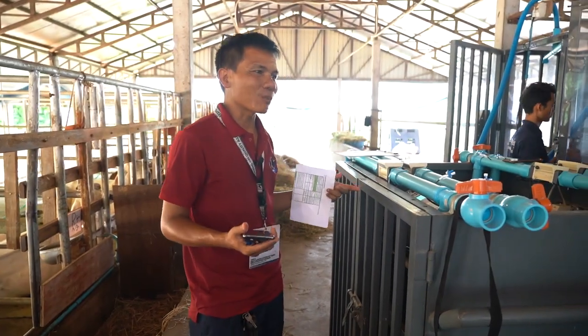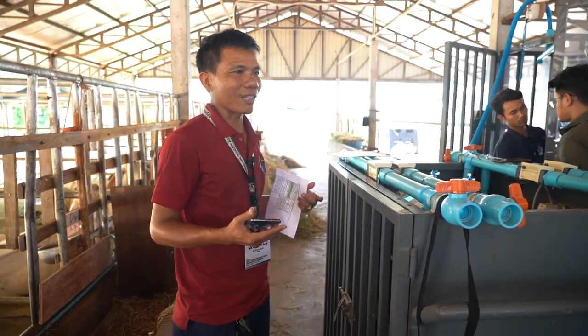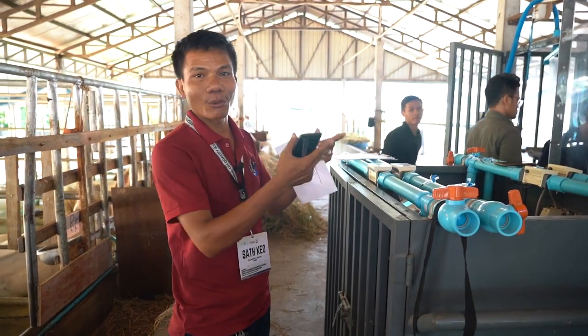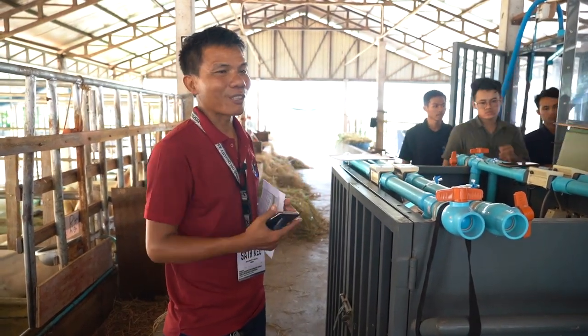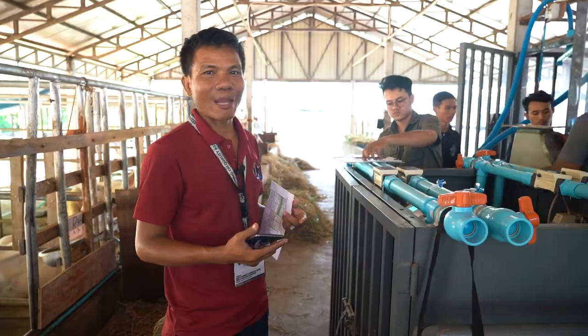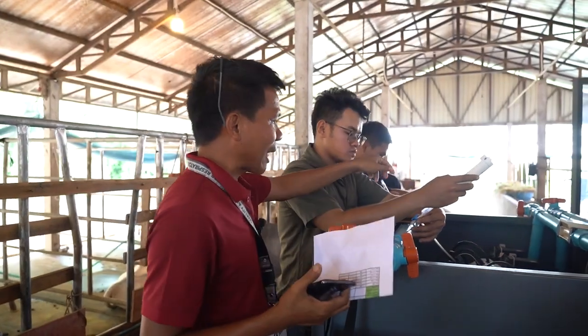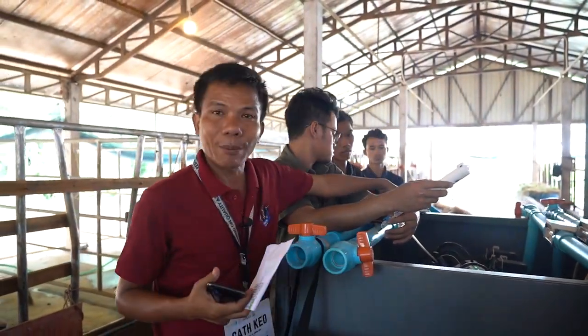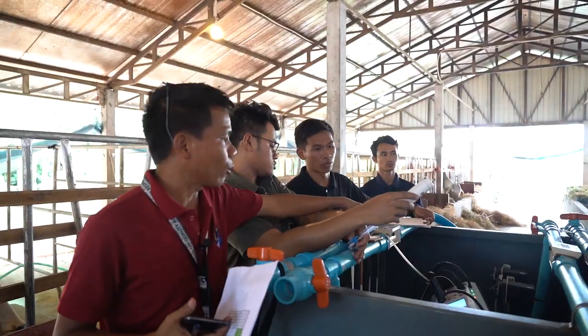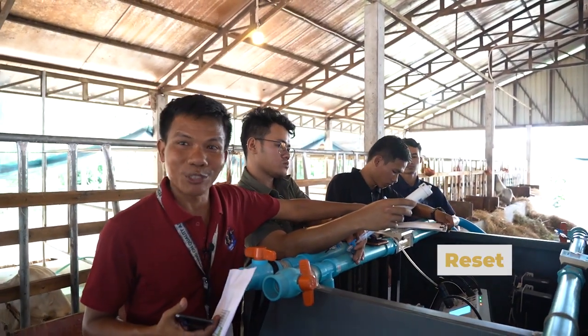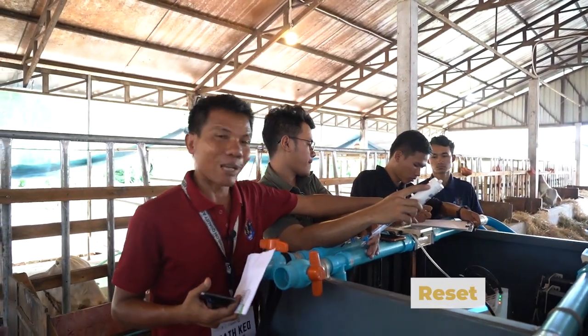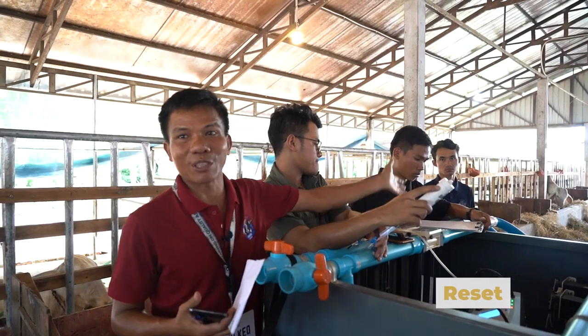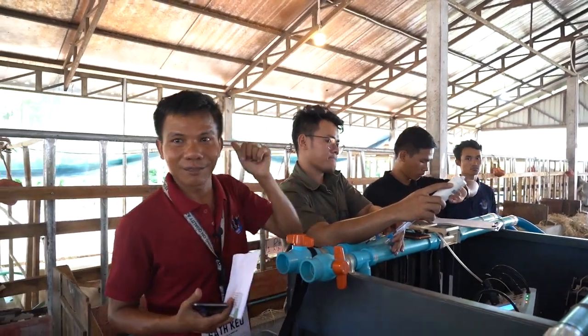So the process of doing the recovery test is the same from one box to another box. Before we start, we would like to have the air flow rate at 0, so we reset the air flow rate to 0, and then we start measuring every 30 seconds.